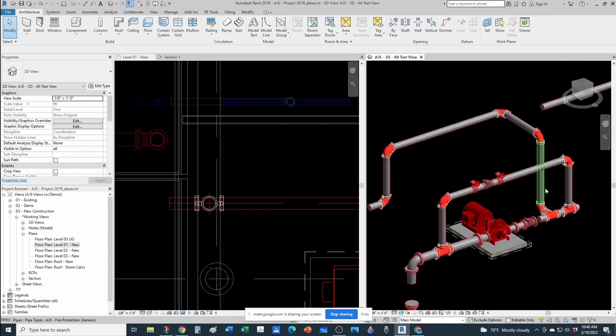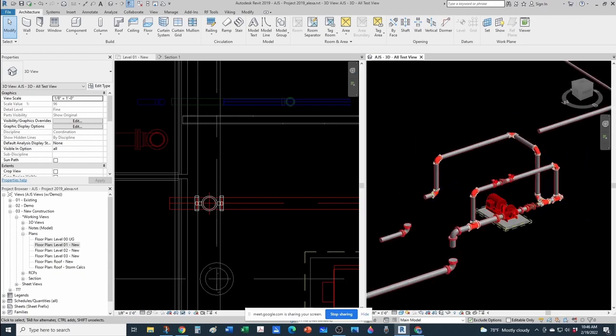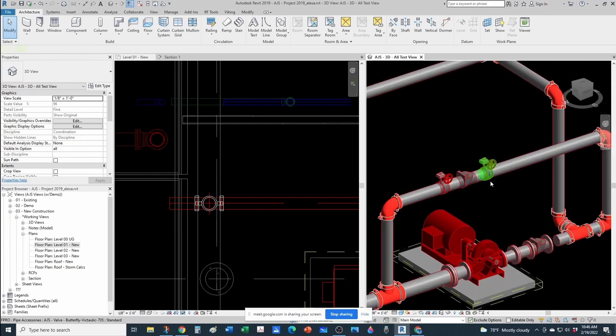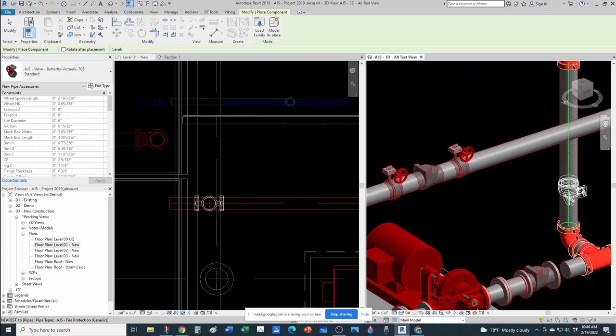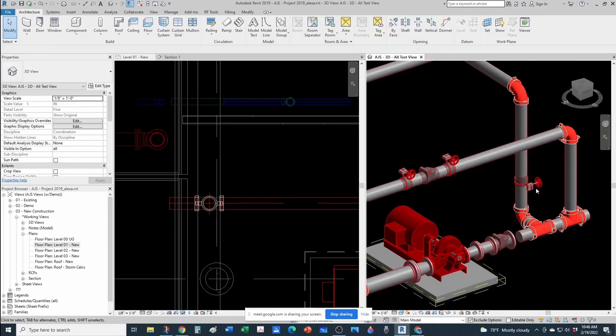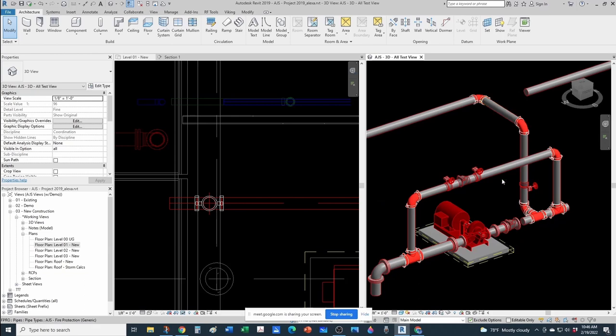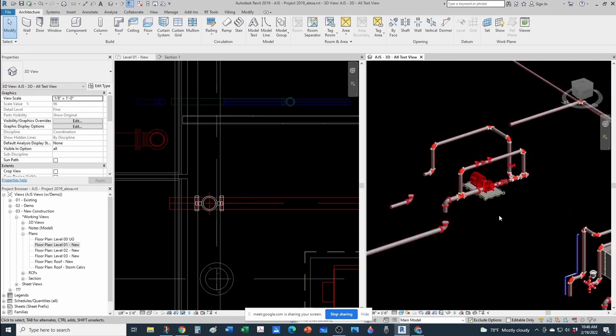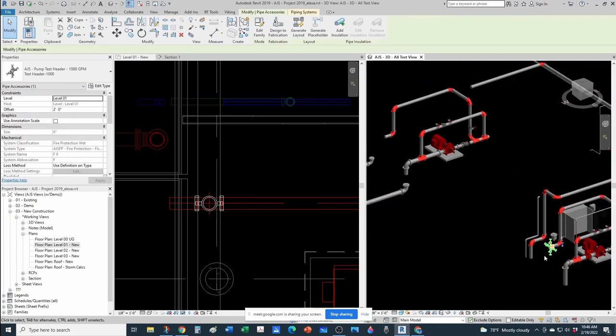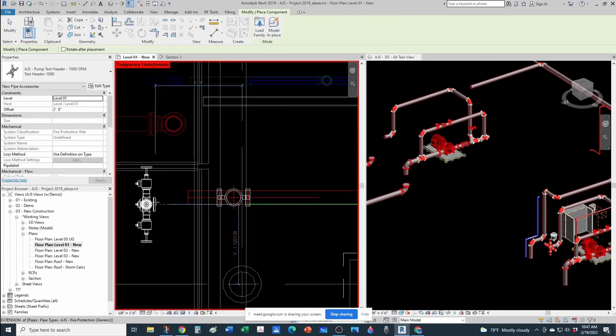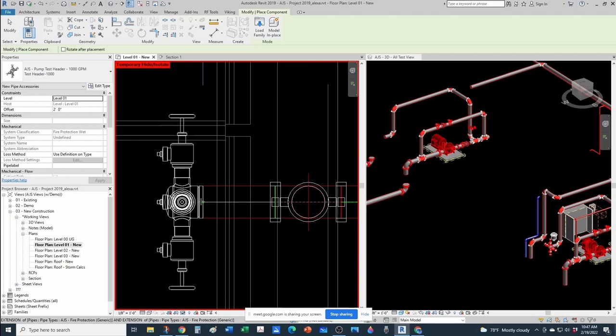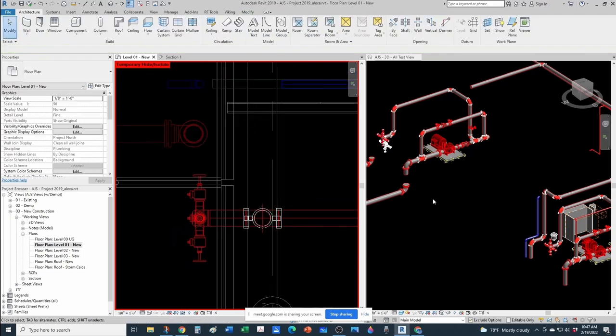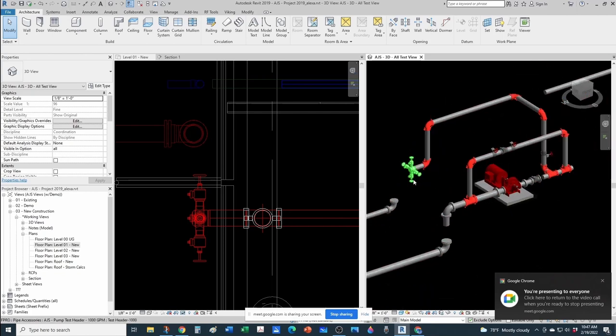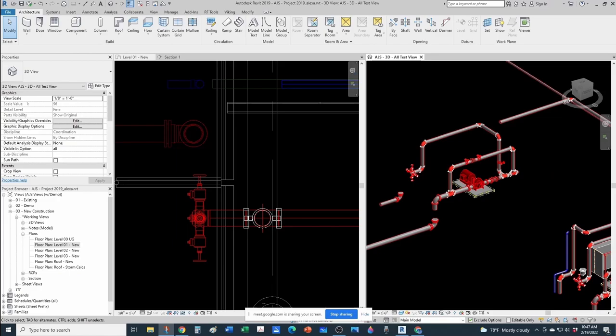We need to have an isolation valve also for our test header, right? So I'm gonna place it, I'm gonna just copy this one here. And I use the create similar command a lot because it saves me a lot of time. So that's my valve right there. You have to orient your valve for service, right? So I could put it all the way up here if I wanted to, but then you will need a ladder to access it. So it's all about layout. Nothing else, we can just provide our test header right here. So for that, I'm gonna create similar here, but for the sake of time, get things going. So I can connect right here, and that's my test header. Let's keep going here. So that's my test header right there. We need another isolation valve.